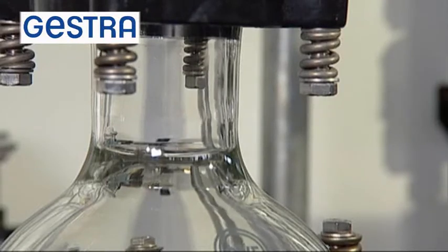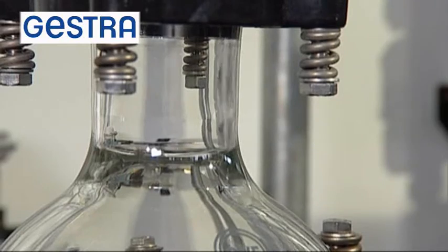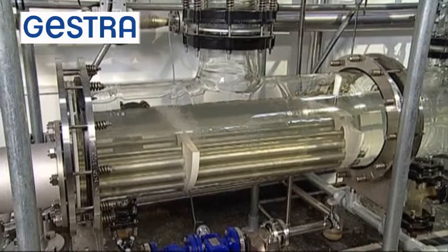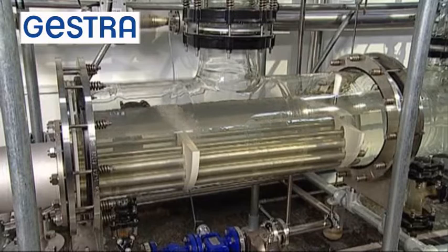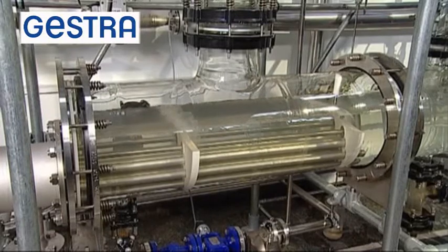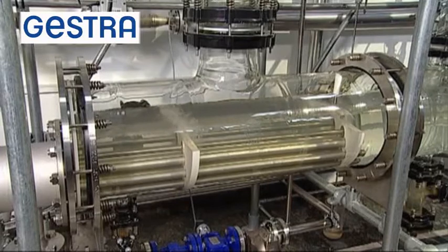At the glass surface, the saturated steam releases heat and condenses. The condensate creates a film of water on the glass surface and then flows down into the steam generator again. A major benefit of the shell-type boiler with its large water space is its ability to store and immediately deliver the steam as required, for example when there's a strong demand for steam.